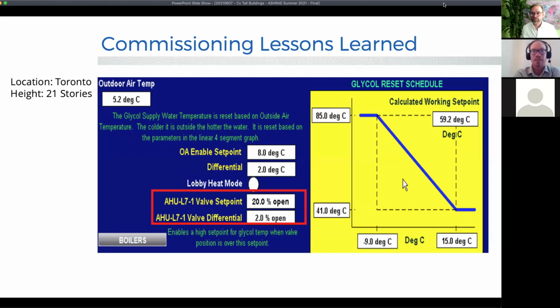So what we did in this case was go in, take some measurements, and make changes to the makeup air units. We quantified exactly what was happening exhaust-wise with an air balancer, including some retail and food court variability we had to measure. We were able to increase the VFDs on the makeup air and pressurize the building better. It certainly wasn't perfect, but it was better, and the litmus test was that the folks on the retail side were clearly more comfortable. We were able to get a win on this one.